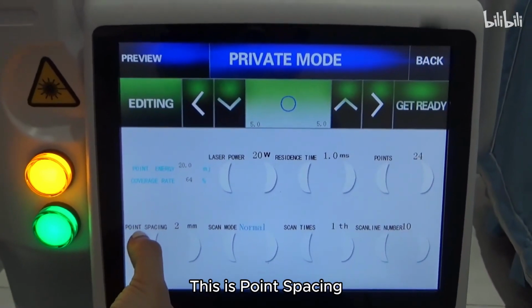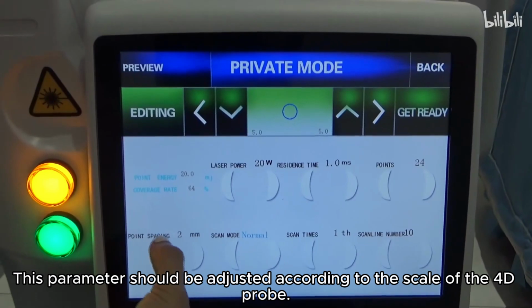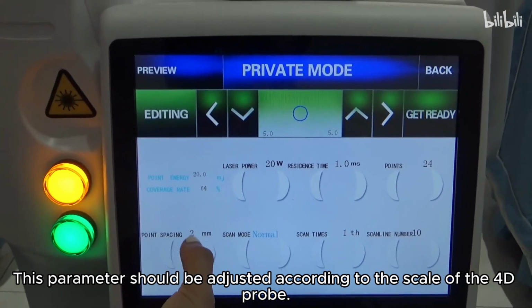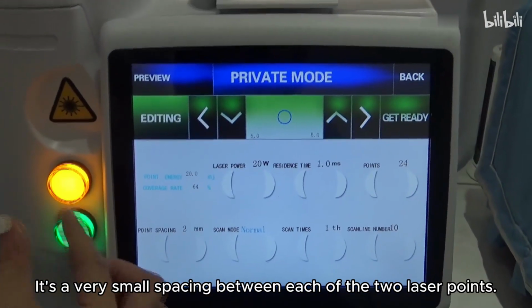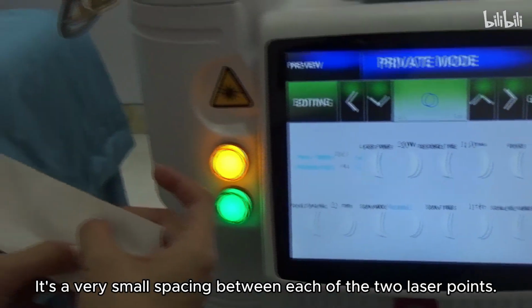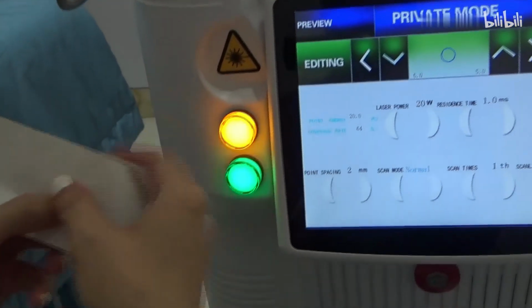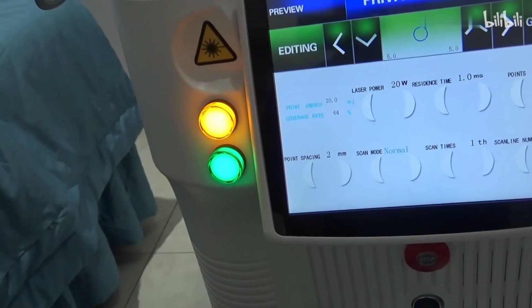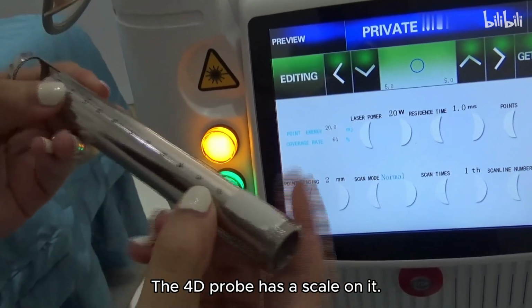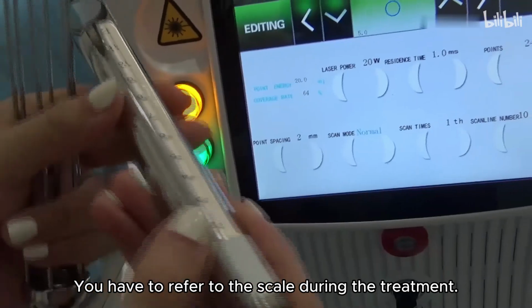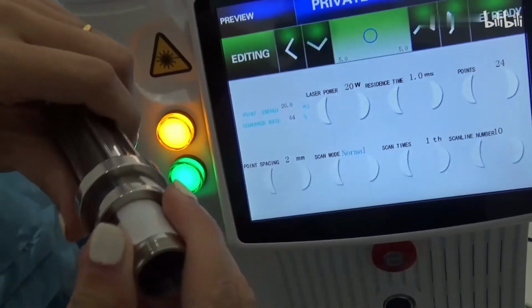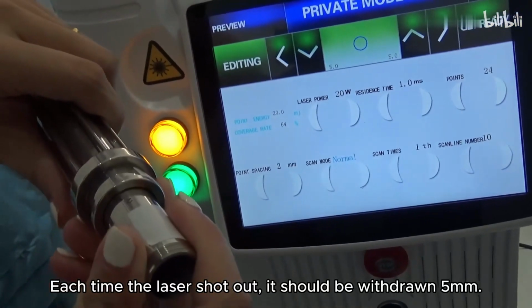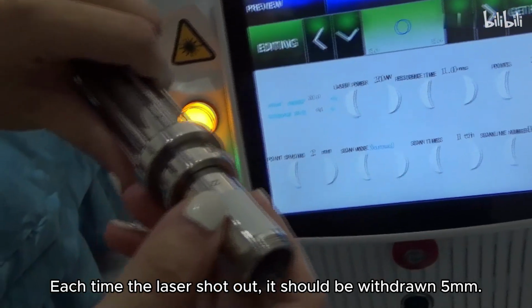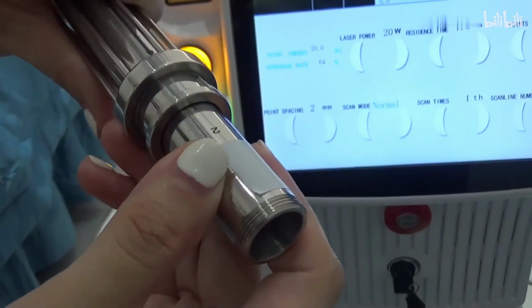This is point spacing. This parameter should be adjusted according to the scale of the 4D probe. It's a very small spacing between each of the two laser points. The 4D probe has a scale on it. You have to refer to the scale during the treatment. Each time the laser shot out, it should be withdrawn 5 mm. Like this.